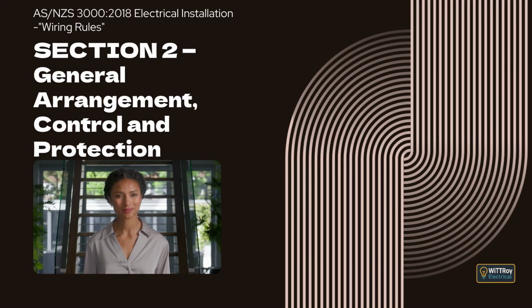Other locations also need RCD protection where socket outlets are used for handheld equipment. This includes outdoor areas, unsupervised public places, and amusement arcades. Some situations are exempt. If another method of fault protection is already used, such as separated supply or extra low voltage, an RCD may not be needed.